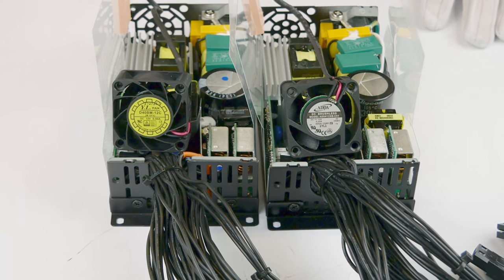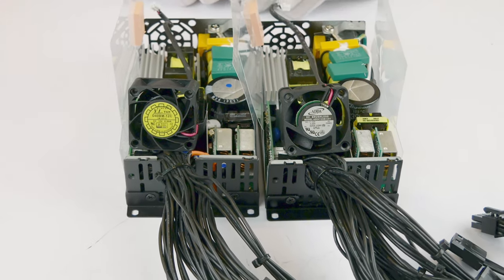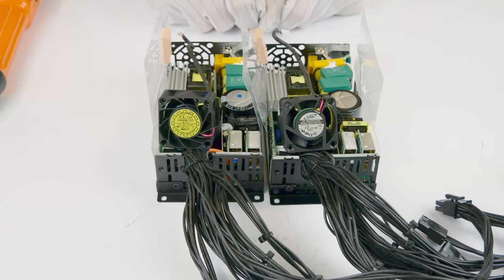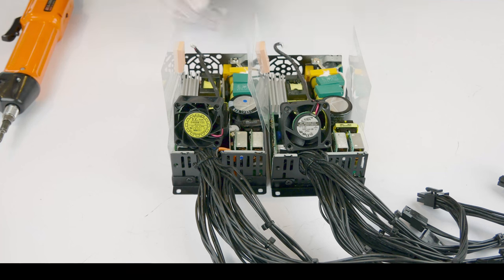One thing to point out though, that noise measurement is very subjective. Fans are normally tested in an anechoic chamber to a standard that defines which side they are measured from and from a distance of 1 meter. Anyway, we get a little bit of digression there away from it. But what does this actually mean?